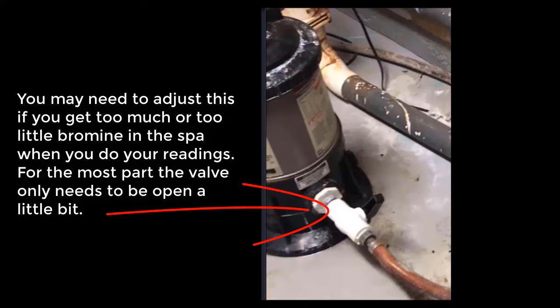If you're getting too much bromine in, you've got to close it off a little bit, because there's always a little bit of a backup from the brominator, and if it sits too long, especially if nobody's in it, then you're going to get a high level of bromine, so you have to cut back on that. And just never leave that brominator valve completely closed overnight, or else you won't have any bromine in the spa in the morning.